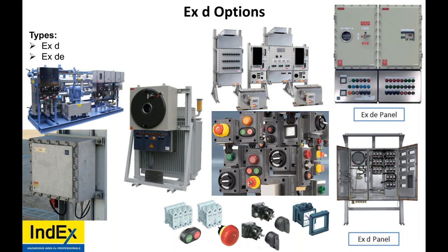What is the difference between testing a component for a U and a full certificate? The U certificate is just an empty enclosure. That empty enclosure for testing doesn't have a temperature rating yet. It'll have a gas group, but you won't know the temperature rating until the equipment has more equipment installed, and then while it's under load, during factory acceptance testing, they would put it under 100% load, and perhaps apply faults and see what temperature that device can get up to. Then they would certify to what temperature that would be good for and any other conditions of use.